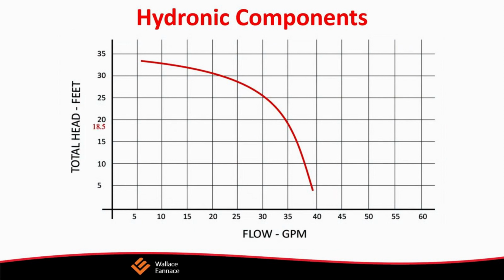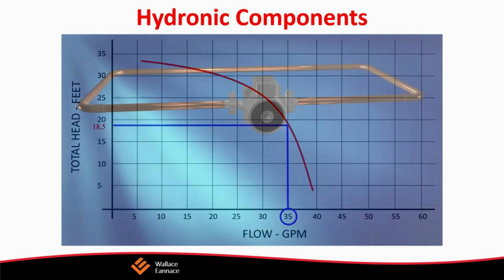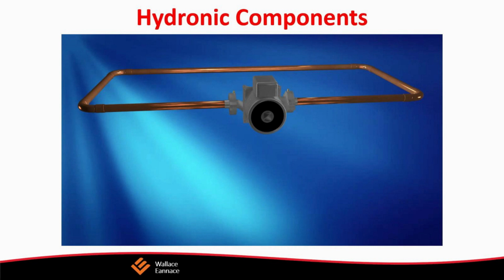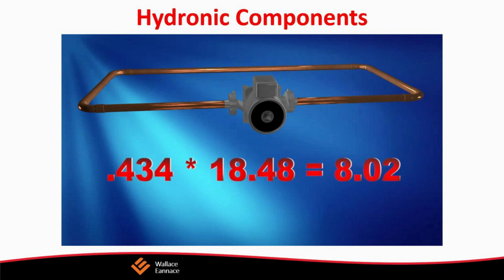It's really that simple. But how much flow are we dealing with? Do I need a fancy flow meter to determine flow? No. All you need is a pressure gauge and a pump curve. A pump curve is a chart provided by the pump manufacturer. This chart shows feet of head on one side and gallons per minute on the other. In the middle of the chart, you'll see one or more curves. These curves represent the impeller size of the circulator. Some charts will have multiple sizes shown on a single chart. Some charts will only have one curve.